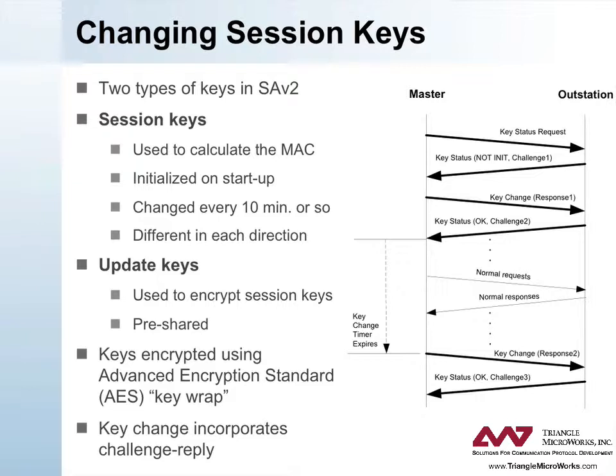The update key is the key used by the master to encrypt the session keys each time they are initialized or changed. The update key is the pre-shared key previously discussed. DNP3 SA-V5 provides a method to manage the update keys remotely. The update key uses the Advanced Encryption Standard, AES, to encrypt the session keys so they cannot be viewed by an attacker as they are downloaded to the outstation. This encryption, plus the frequent changing of session keys, prevents attackers from analyzing the traffic to guess the session key in time for it to be usable.